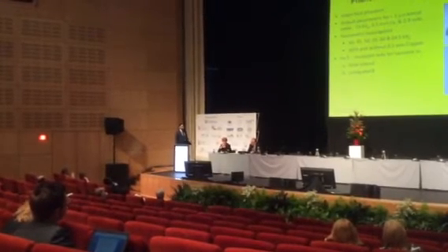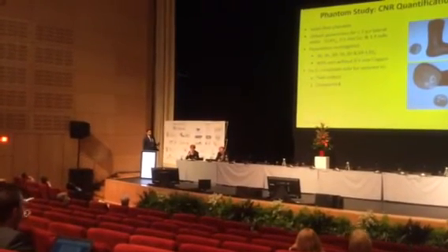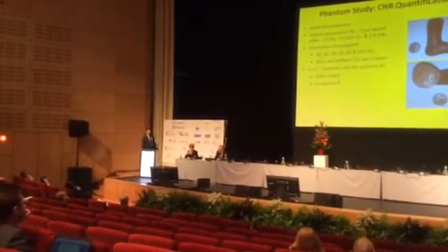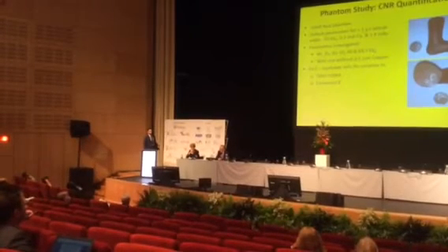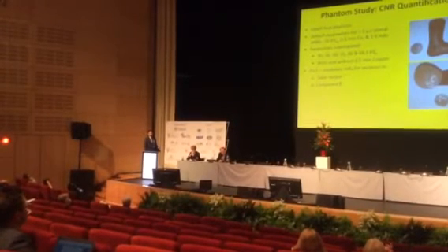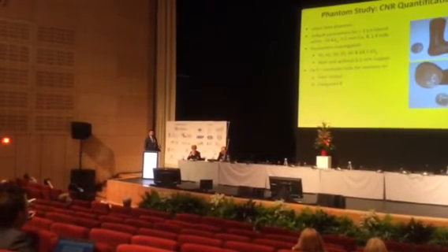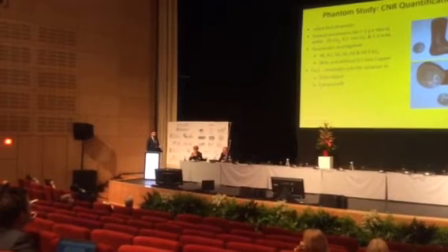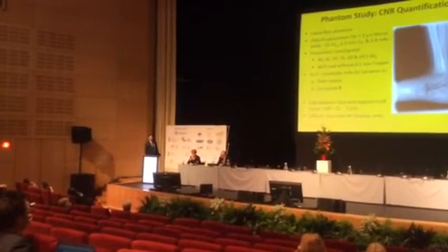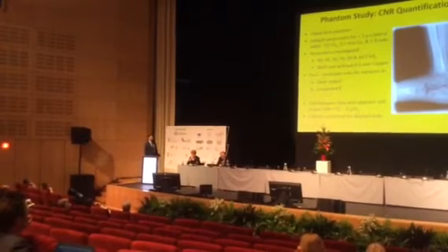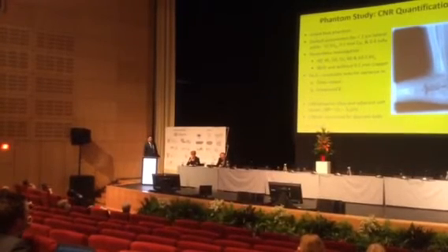I then exposed the phantom to a range of different kVs between 40 and 64.5, with and without the presence of this additional filter. But what I managed to do was actually fix the effective dose for all of these exposures by modulating the mAs for firstly the tube output differences, and then secondly the computed effective dose variances across the different beam qualities. And then the contrast to noise ratio was simply measured by tracing a region in the distal end of the tibia and then one in the adjacent soft tissue.